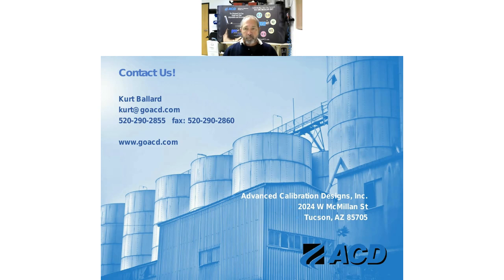From Mayank: I need a hydrogen chloride cell for my Cal 2000. Is it possible, or do you have another solution? No, right now you'd have to use a surrogate gas. Most people calibrating with HCl are using, depending on the manufacturer of the sensor, either H2S from us or chlorine and a response factor. I don't have HCl right now. Do you have it in the vials? Yes, we have bump testers for the vials, but we don't have actual calibrators for them. Okay.